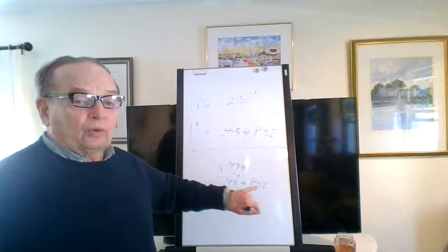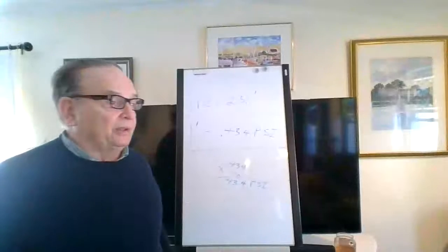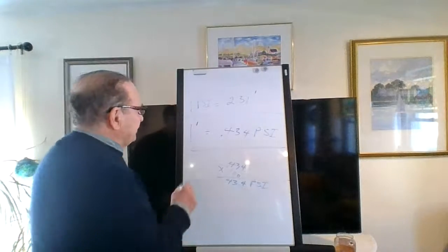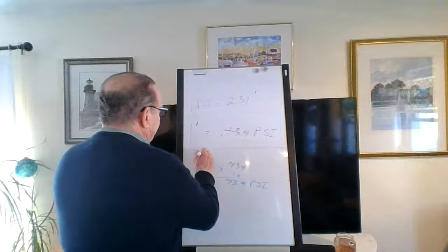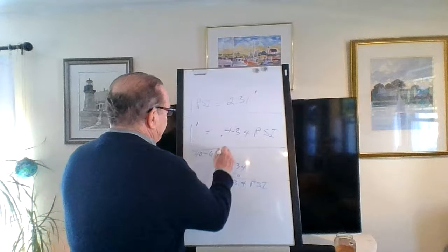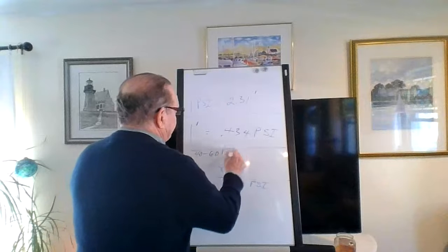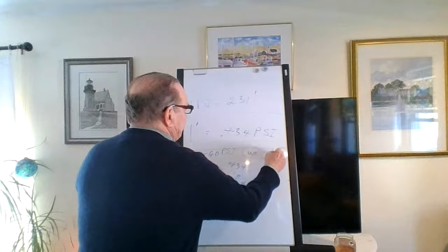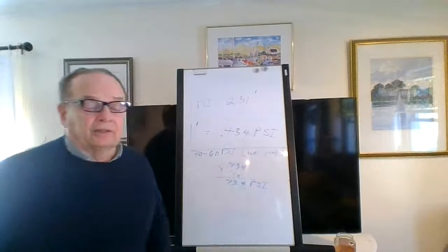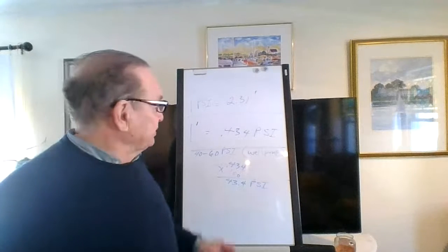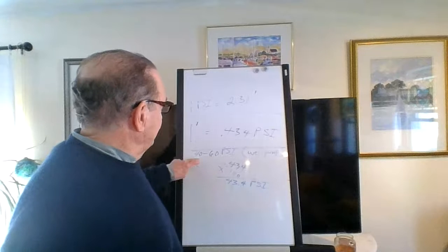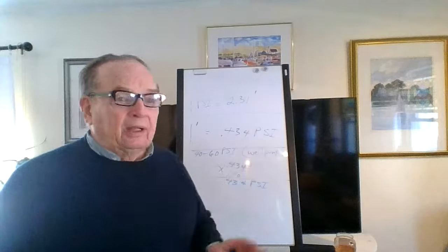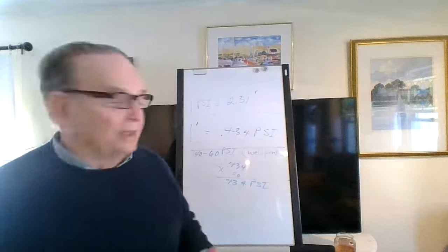Now, what if you're doing a well pump? Okay, now we did well pumps one night, a couple months ago, and remember, I would say 40 to 60 psi. This would be for a well pump. That's the setting on that Square D switch. You guys have done well pumps. I suspect that we're going to be talking roughly the same pressure here. Your bosses are probably in that ballpark, within 5 pounds one way or the other. I found this to be good.